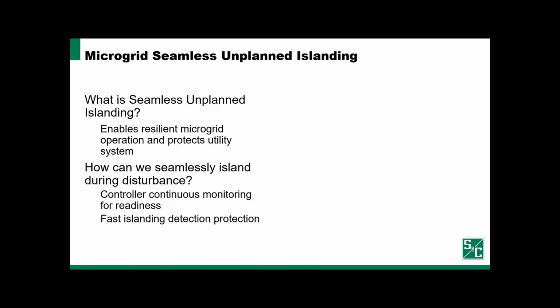Seamless unplanned islanding is an approach here. What this does is, instead of disconnecting individual DERs for a system fault, we will disconnect the entire islanded microgrid system to separate all of the DERs simultaneously from the system fault but also keep those DERs online and available to supply the islanded microgrid system. This involves a combination of a higher level controller, which is monitoring system status and ensuring that the resources are always dispatched such that they can support the microgrid if an islanding situation came up, and fast protective devices that are detecting an event very quickly and operating.